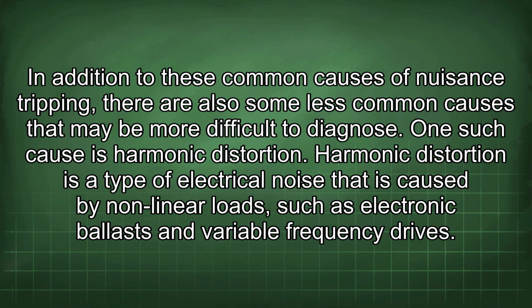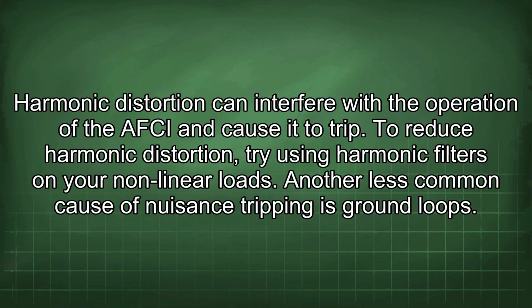In addition to these common causes of nuisance tripping, there are also some less common causes that may be more difficult to diagnose. One such cause is harmonic distortion. Harmonic distortion is a type of electrical noise that is caused by nonlinear loads such as electronic ballasts and variable frequency drives. Harmonic distortion can interfere with the operation of the AFCI and cause it to trip. To reduce harmonic distortion, try using harmonic filters on your nonlinear loads.